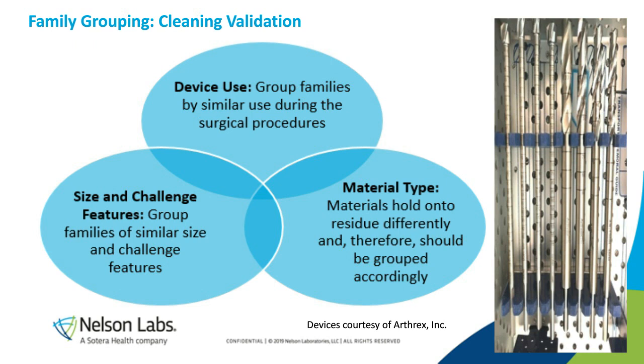A titanium device requires different processing than a polymer device with silicone or other soft plastic parts. Another example is devices that are 3D printed represent unique considerations because they are typically very textured and porous and thus more likely to hold onto residue. The third way to determine grouping of devices is looking at size and challenge features, in which the considerations that are employed in this type of grouping include components and product design and size.